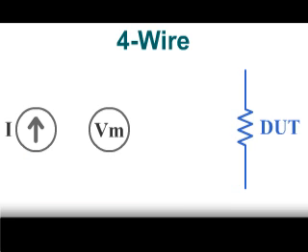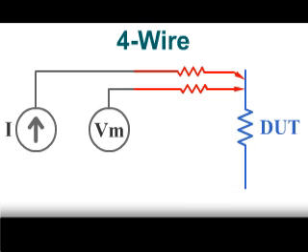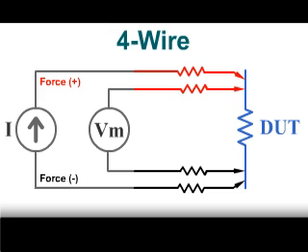With 4-wire or Kelvin testing, two wires go to each side of the wire being measured. One is the current force wire, the other voltage measure or sense wire.